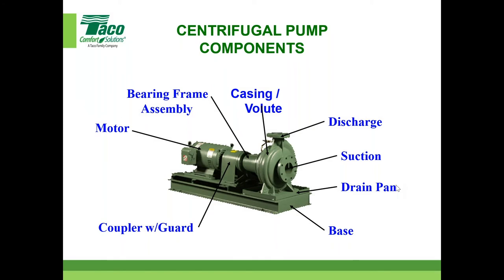Again, the correct piping going in here. Most pump manufacturers offer what we call a trim or a suction diffuser. It's a piece of equipment, a product that has straightening vanes in it, so it makes sure the water goes in nice and laminar. So there are no rushes of water, no twisting, and no air getting in there. Or you just need 5 to 7 pipe diameters with a long radius elbow to properly design that. So it's just some important basic stuff that should always be considered or shown on your details in your MEP files or whatever. Just some recommendations there.